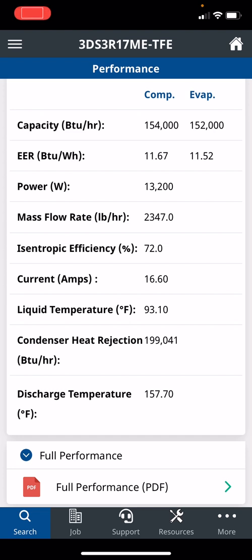How much power? 13.2 kilowatts. The mass flow rate of that refrigerant, the BTUs per hour is pushing through there. The actual current amps at those conditions, 16.6, and then down below here, the discharge temperature.